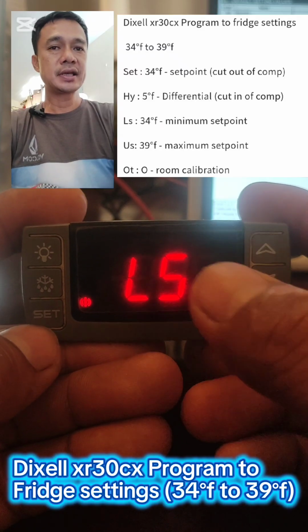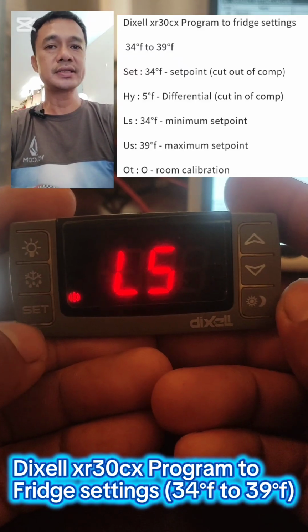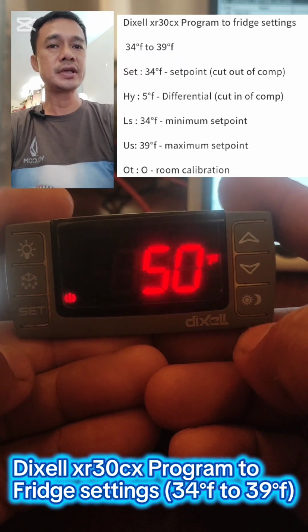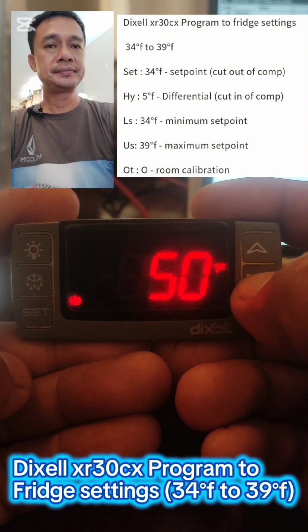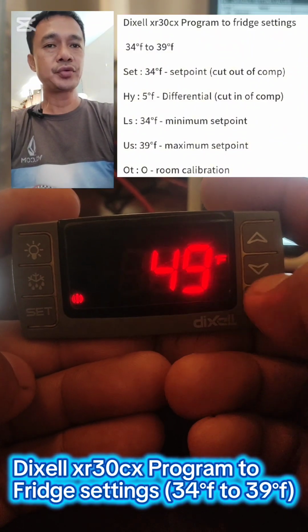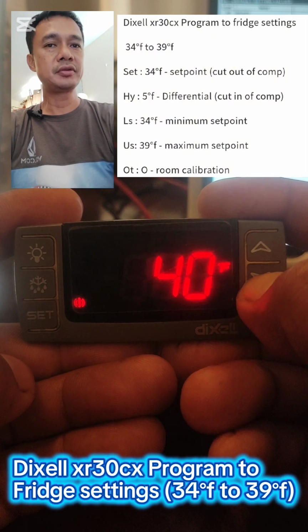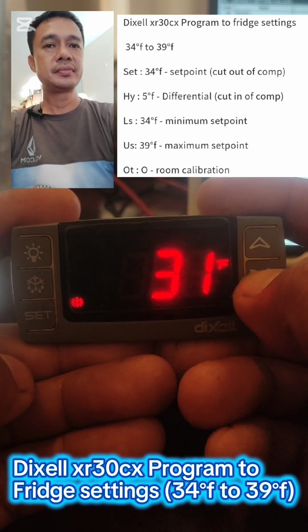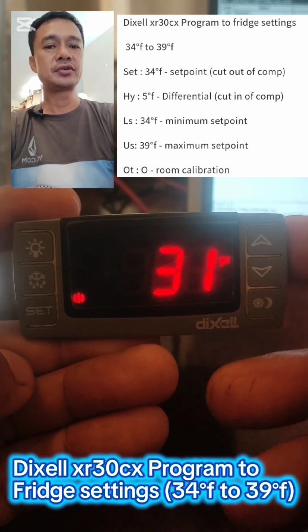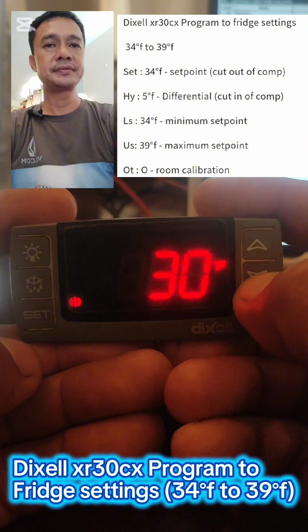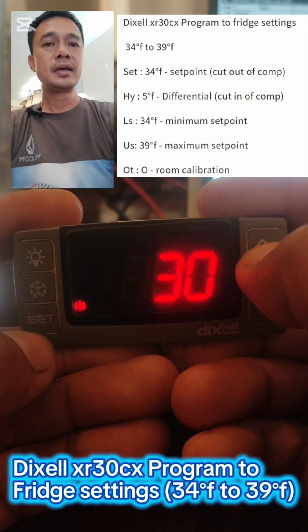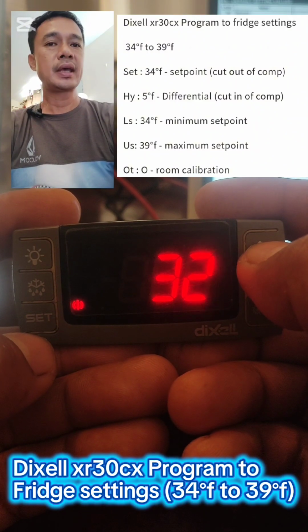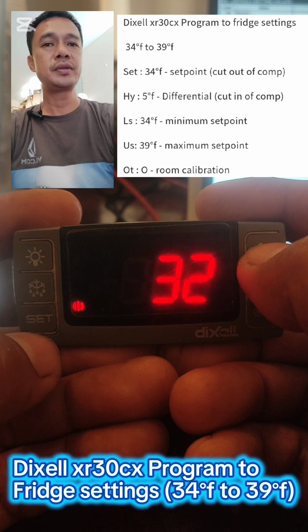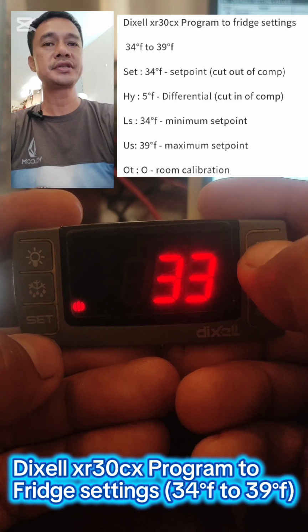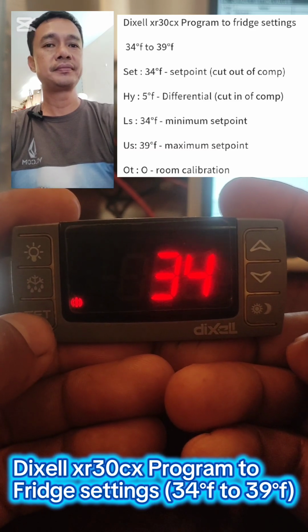And next is LS. LS is the lowest set point. Press set. And this program is from the condensing unit. They use this control for the condensing unit. And my LS is the same as my set point. Therefore, this is 34. Then press set.